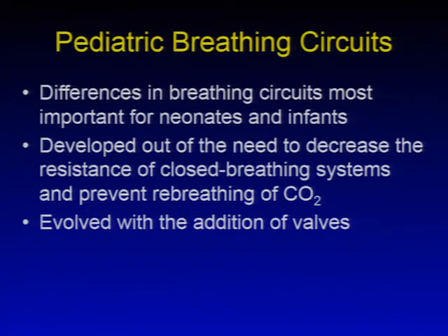Once the child is intubated, a breathing circuit is used. The differences in breathing circuits are very important for neonates and infants, as increased resistance to flow is a major concern based on the decreased radius of the infant's trachea, as well as their need to have higher work of breathing. The circle systems nowadays have modern valves, and associated with a sophisticated ventilator, there has become less need for Mapleson-type circuits, but I will briefly review them here.